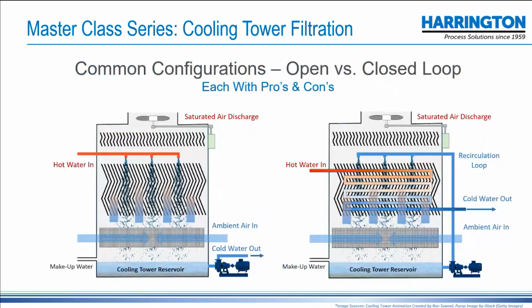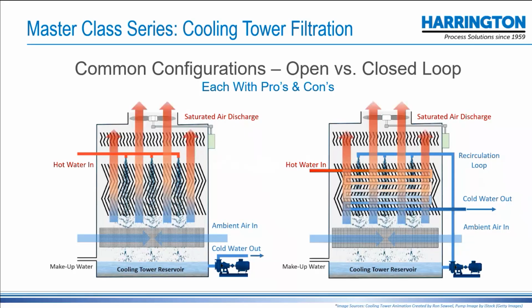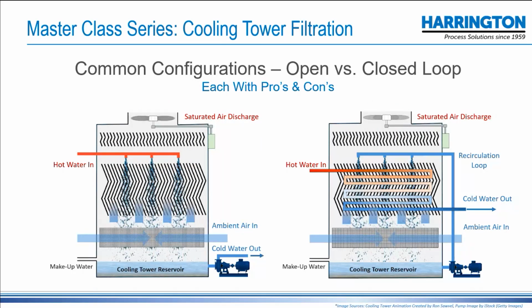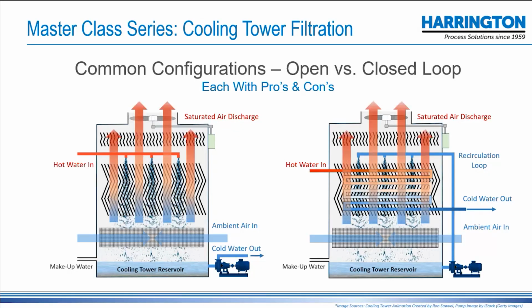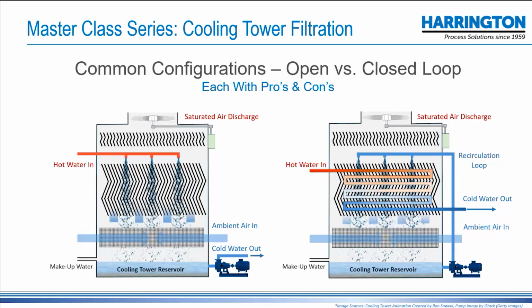So there are all kinds of cooling tower types and configurations. We can only really concentrate on a couple of them, and really we're going to concentrate on the one that is most common. So there are two basic types. The one that you see on the left is an open loop cooling tower. Hot water from the plant comes in, goes down through the dispersing elements, and has an upflow of air that causes evaporative cooling. That cold water then falls to the basin reservoir, and from there it's pumped straight back to the plant. That's an open loop.